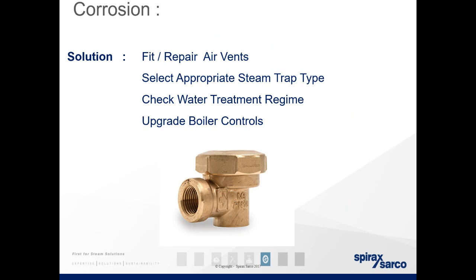Again, if you start seeing that traps need to be maintained more often, that could be an indication that there's more erosion happening, which could be an indicator of carryover. And wetter steam as well: if you're not seeing the heat transfer you expect, there is the potential that you're getting carryover, or at least a build-up of condensate. Condensate is the enemy in a steam pipe because it acts as a barrier to heat. So it could be an indication you've got failing traps.